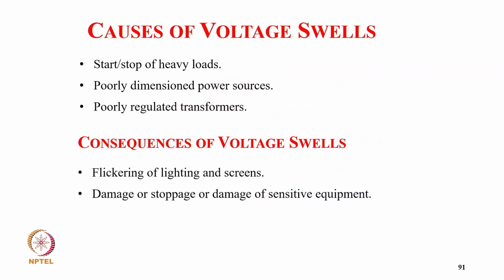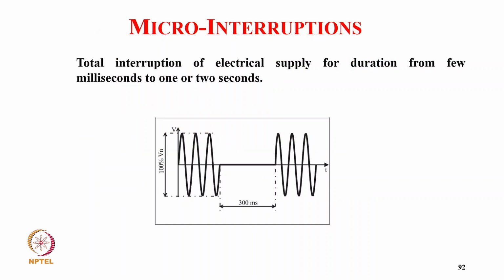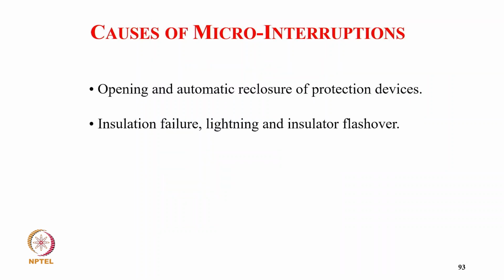Now, causes of voltage swells: start or stop of heavy load, poorly dimensioned power switches, poorly regulated transformer. Consequences of voltage swells: flickering of lighting and screens, damage or stopping of sensitive equipment. Micro interruption is the total interruption of electric supply for a duration of milliseconds to 1 to 2 seconds, as you can see here.